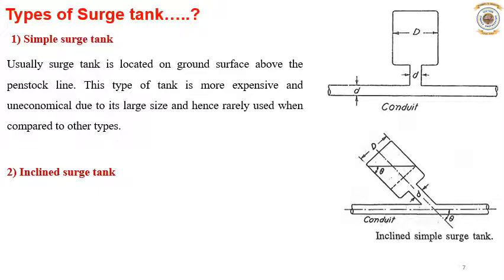So you can see this diagram. Okay, so when the surge tank is inclined to the horizontal, its effective water surface increases, and therefore a lesser height surge tank is required for the same diameter. So you can reduce the length, and you need not worry about the support. Okay, that is one advantage. For the same diameter if it is inclined, or a lesser diameter tank is required for the same height.